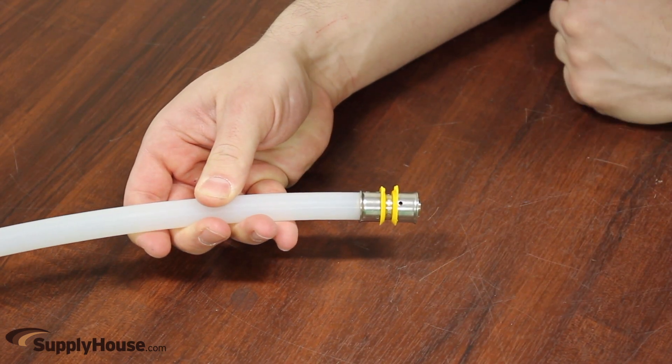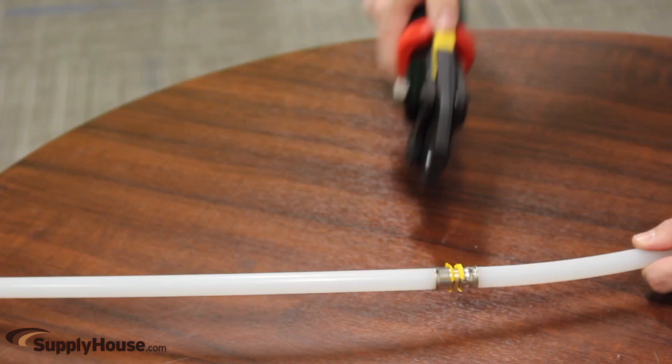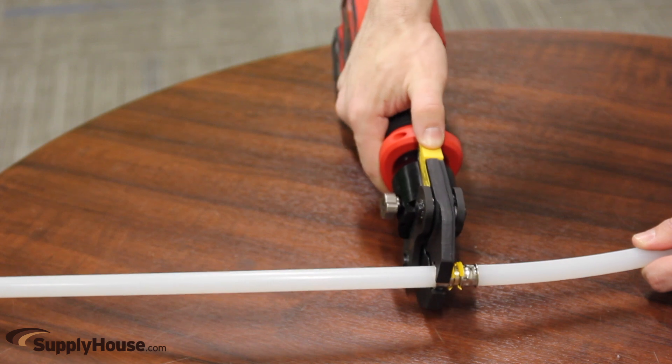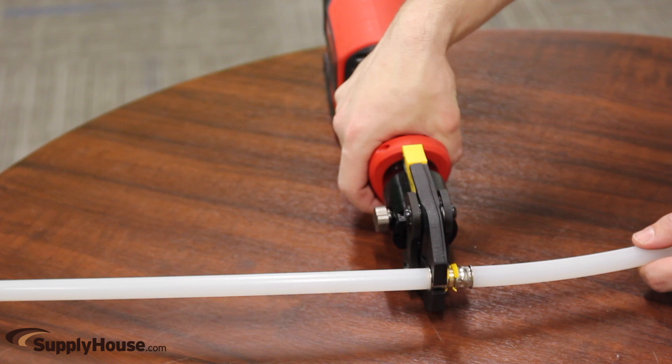Insert fitting with sleeve onto the PEX tubing. Place jaws around the fitting. Properly align the fitting in the jaws — the jaws must fit square to the tubing. Improperly aligned fittings may damage the jaws, generating excessive flash during pressing.